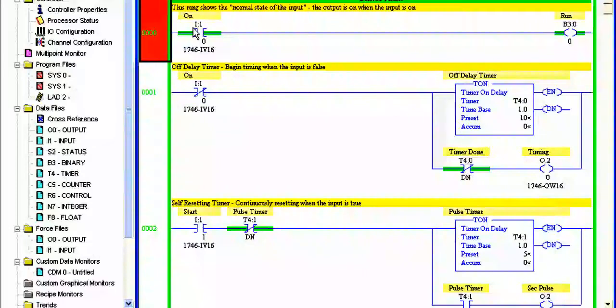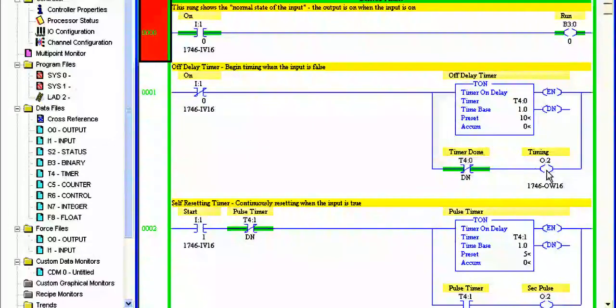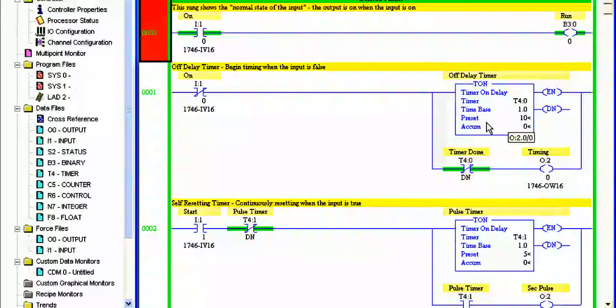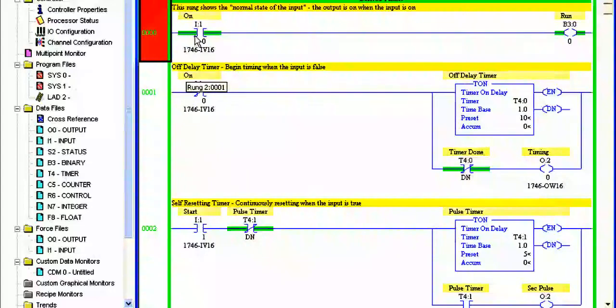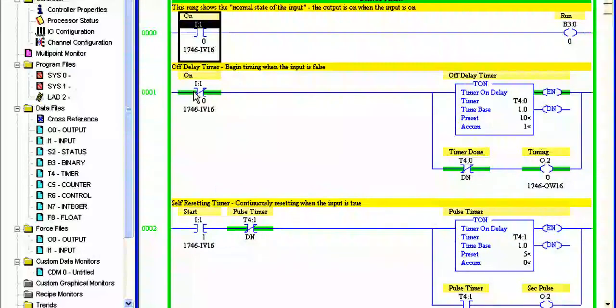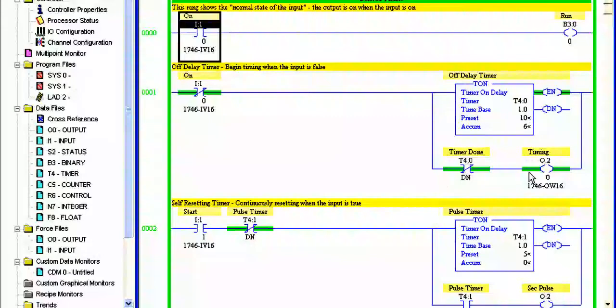This will go true here through the done bit and turn the output on. When the time period is up the output will go off. Now I've got a 10 second time base here so there's plenty of time to talk about it. So I'll use toggle here because I'm using my emulator. So I'll toggle a bit off. Immediately the timer starts timing. We've turned it off, remember we're timing up, the output's on all of the time.